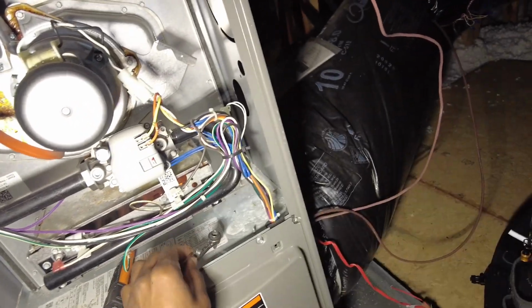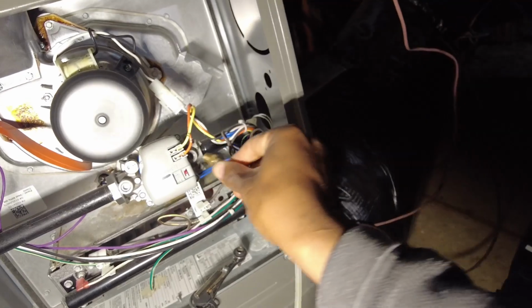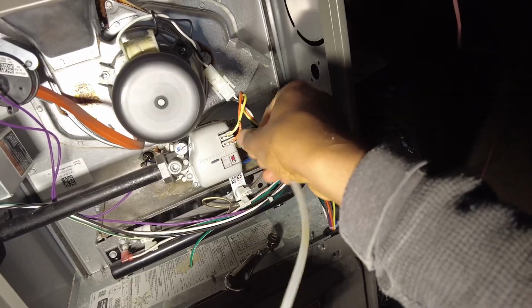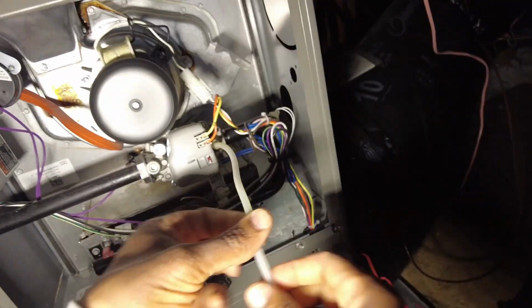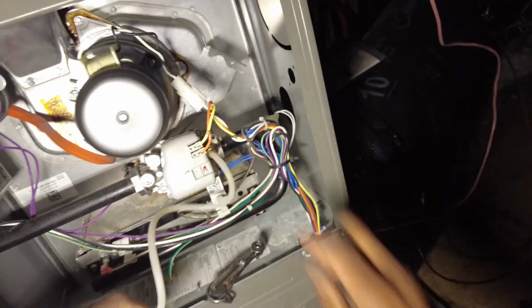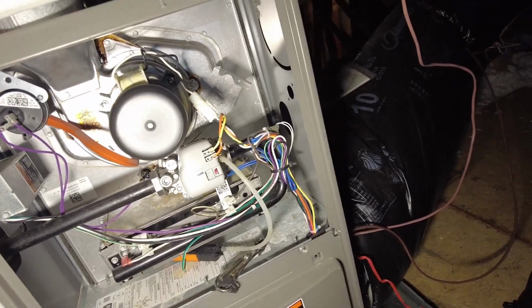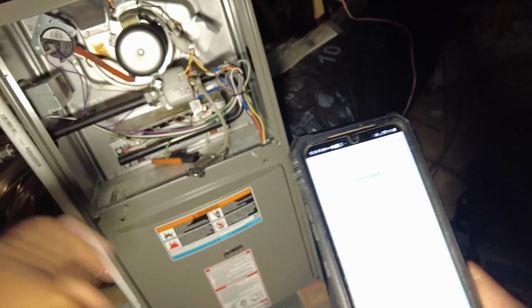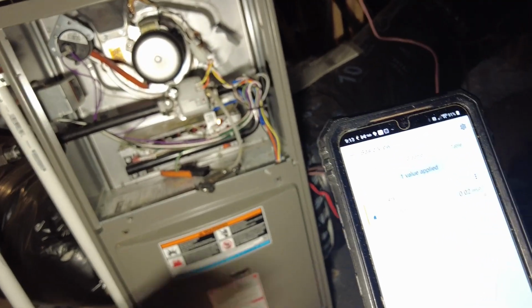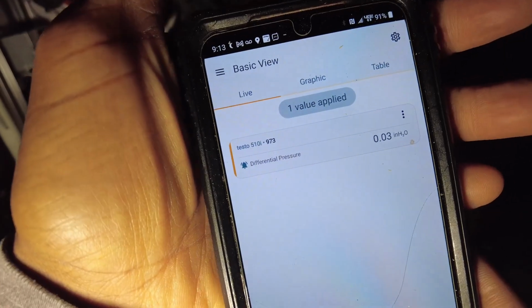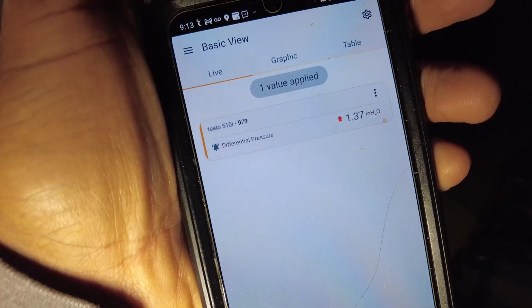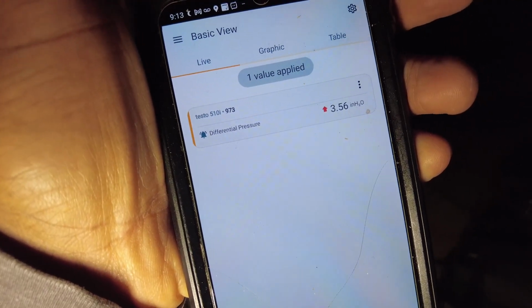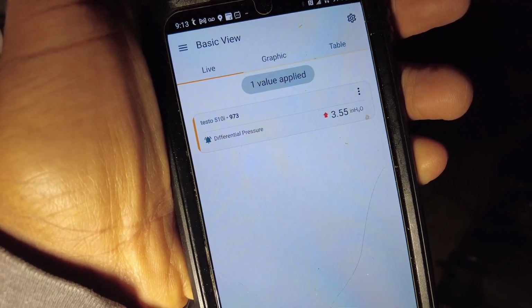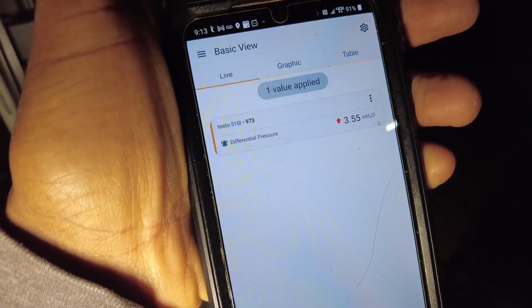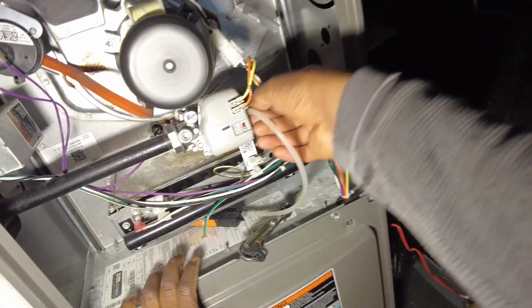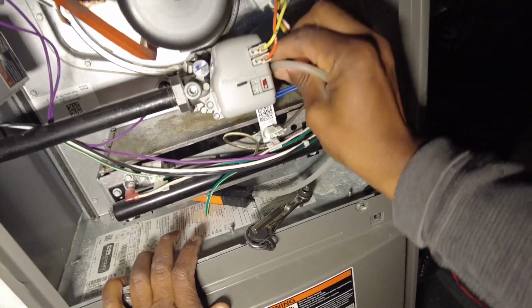Okay. I'm glad it gives you so many attempts. And now we got the manifold. This is called manifold pressure, right? Don't need to go crazy on that, just a quick snug. So we see we got nothing there now. Gas valve, gas pressure's on. Now she's going to give us a little something. So we're looking for about 3.5 inches of water. Here she goes. 3.55, 3.56. Apply that. So we've pretty much finished this system, realistically speaking.